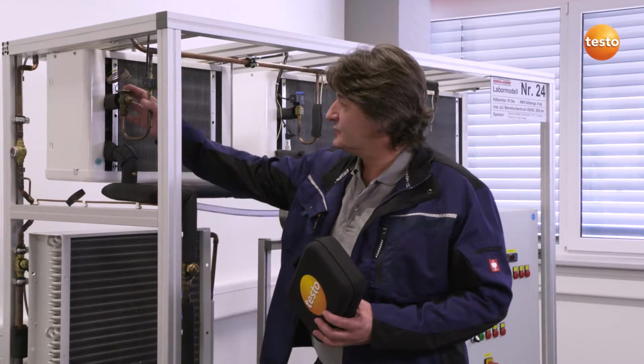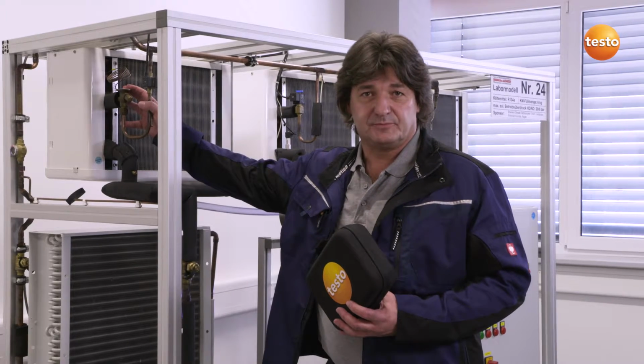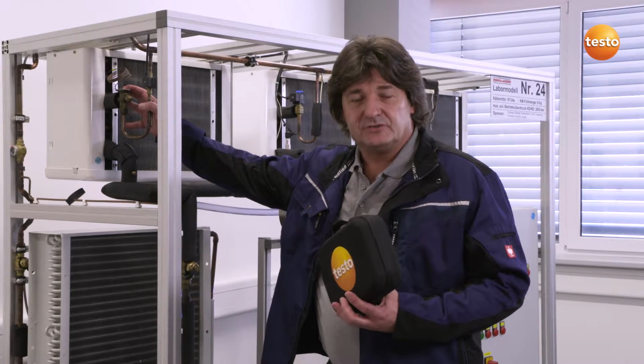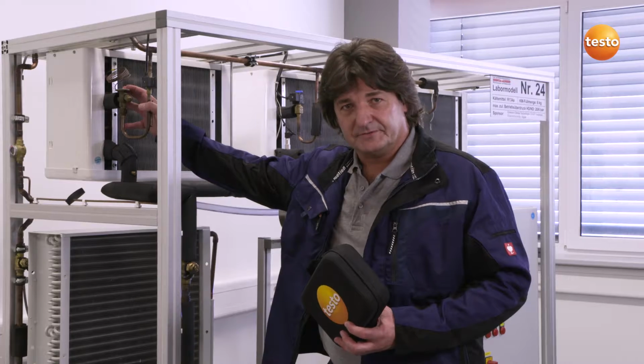I have previously shown you measuring technology from Testo in practice. As a refrigeration and air conditioning engineer, I frequently have to carry out inspections of refrigeration systems. Today I will be using the Testo Smart Probes refrigeration set on this test system to carry out current measurements of superheating and subcooling.